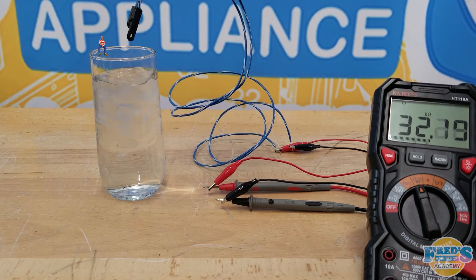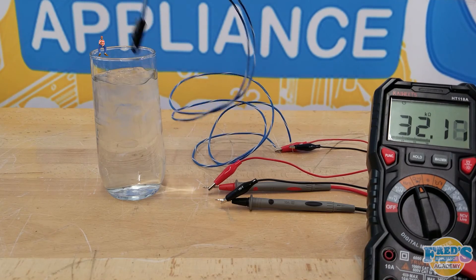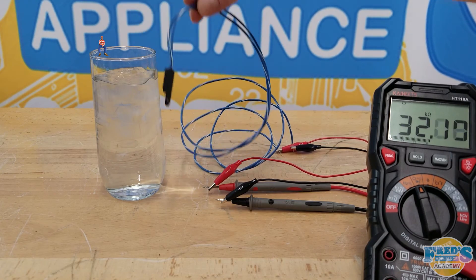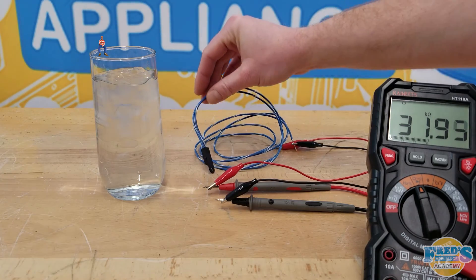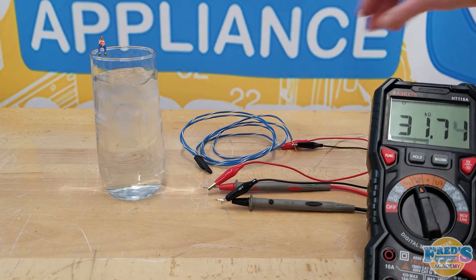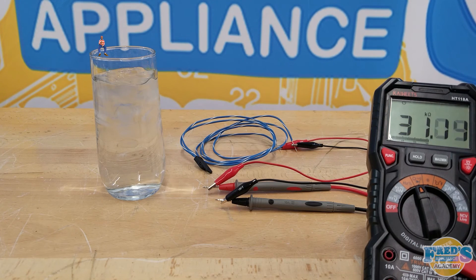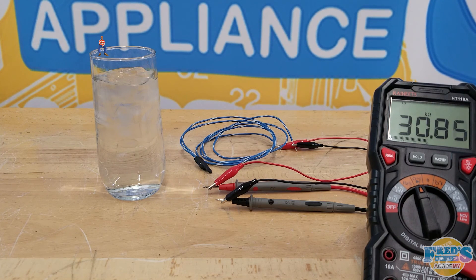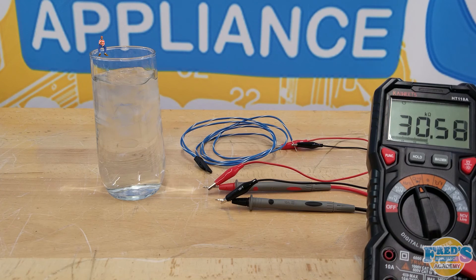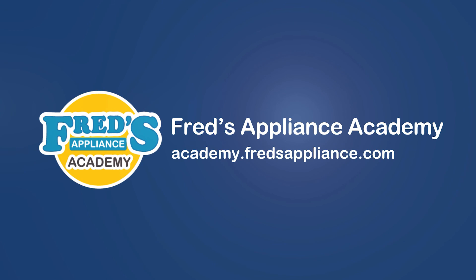Once the thermistor is removed from the water its resistance value should immediately start to decrease. If left out long enough the thermistor should reach room temperature and its resistance value should correlate. This test proves that the thermistor is able to accurately read decreasing temperatures as well as increasing temperatures.